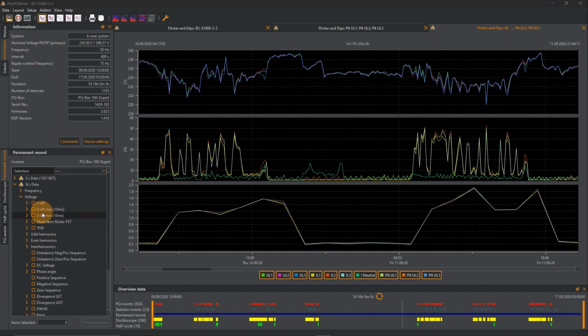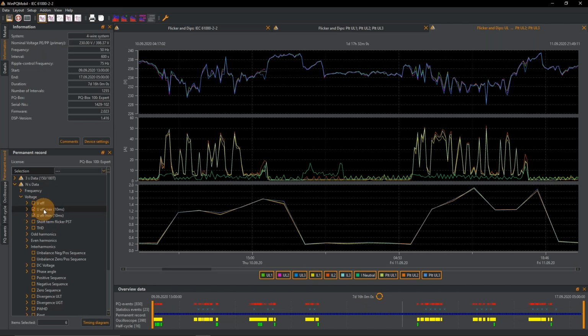So next, I will select my maximum values and my minimum values of the voltage. And I will also select the short-term flicker. Now I'm going to reveal: the short-term flicker is a value that represents the 10-minute flicker value, and the long-term flicker in turn is calculated from short-term flickers, but represents a time over 2 hours. So that's the difference. I will also display the maximum values of the current. I will neglect the minimum values because that's not interesting to me. I want to see the maximum values.